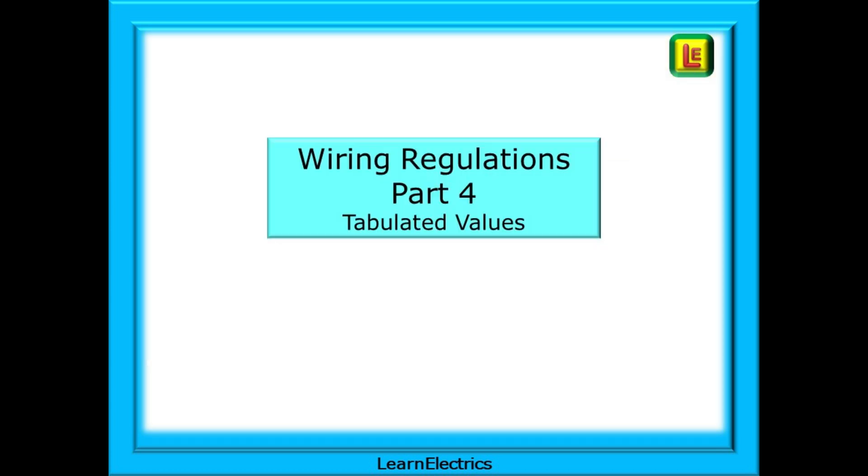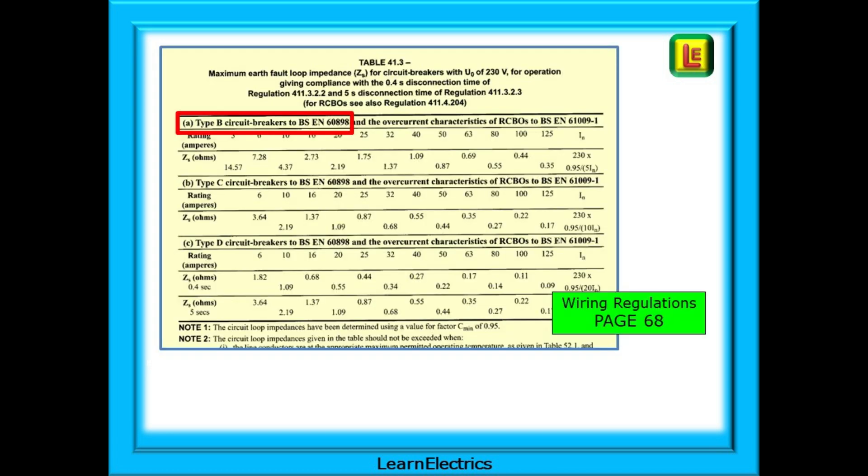Now that we know this, which is what the manufacturer's standards expect, let us look at part 4 of the wiring regulations where we will find tables of ZS values already calculated for us. We will find type B breakers on page 68 in table 41.3. This is the same table for circuit breakers and RCBOs.